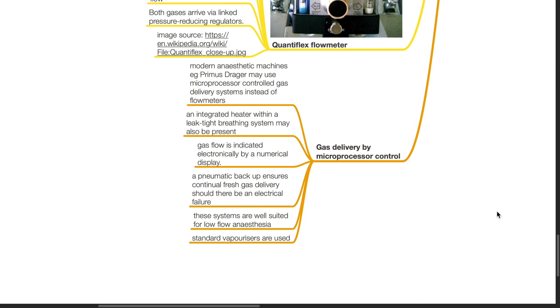A pneumatic backup ensures continual fresh gas delivery should there be an electrical failure. These systems are well suited for low flow anesthesia. Standard vaporizers can be used.